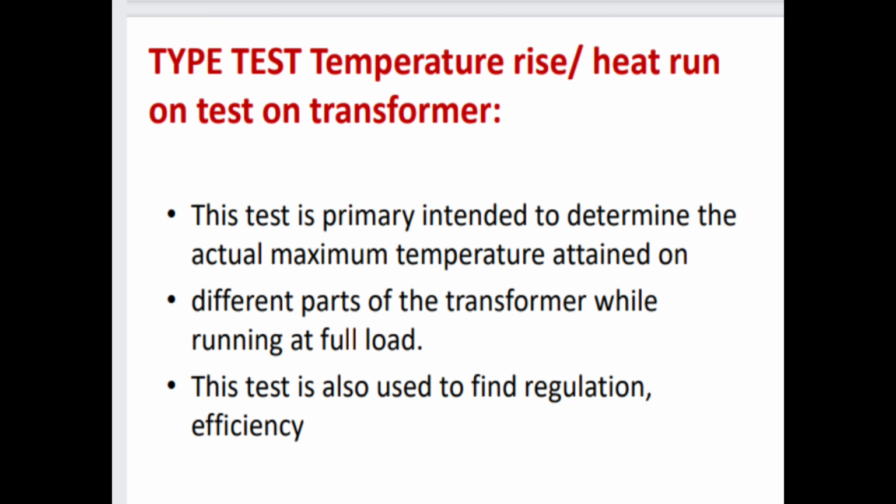In this, the temperature rise or heat run test on a transformer is included in the type tests, and the temperature rise test is also called the heat run test on a transformer. This test is primarily intended to determine the actual maximum temperature attained on different parts of the transformer while running at full load.